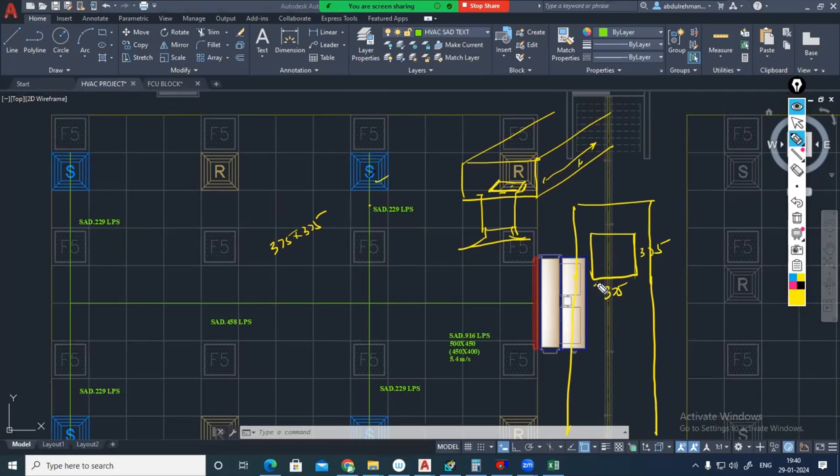If you want to make a 375 hole, the width of this duct should be minimum 375, right? But the problem is, if the hole that you are making is the same as 375, when we are connecting this duct to drop, we will be placing a collar there. In the duct sizing class we have discussed, we'll be placing a collar there. After that, the collar we have to hammer in sideways. We have to hammer it. Hammering here, hammering there. This is not an issue.